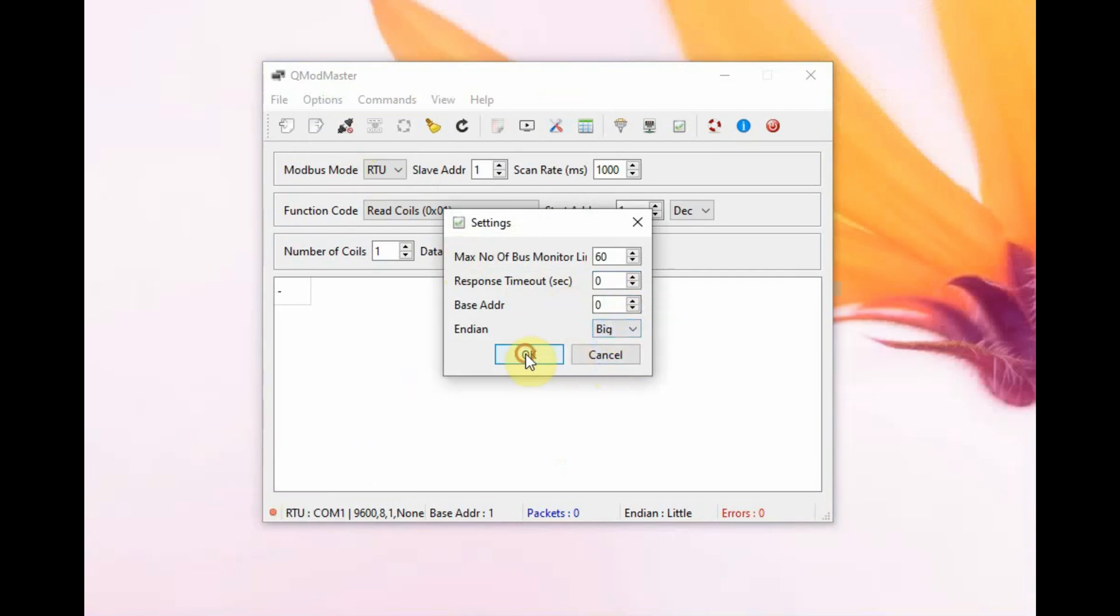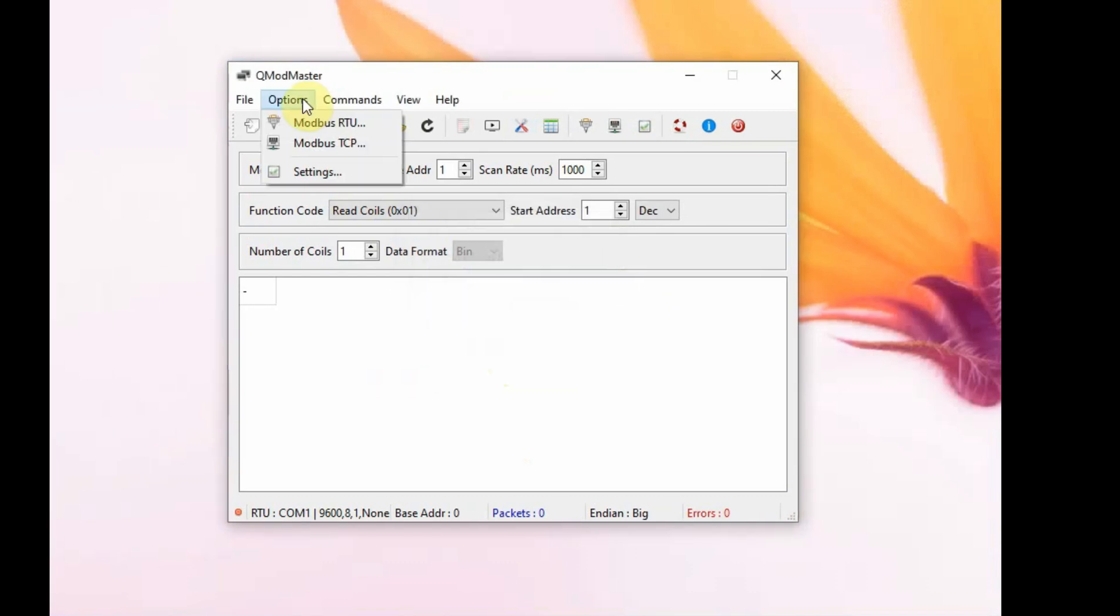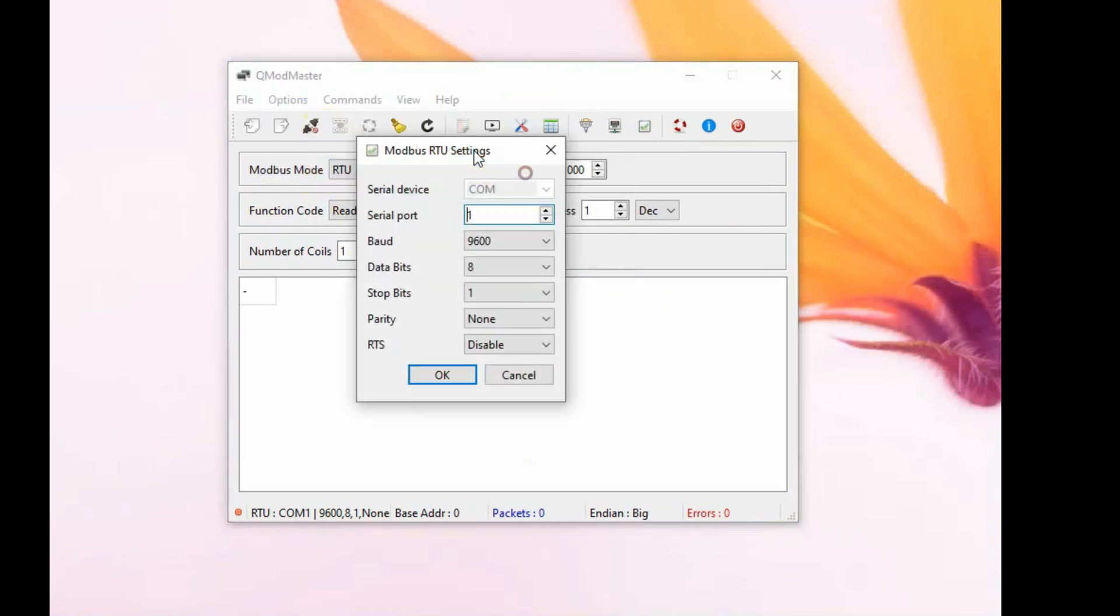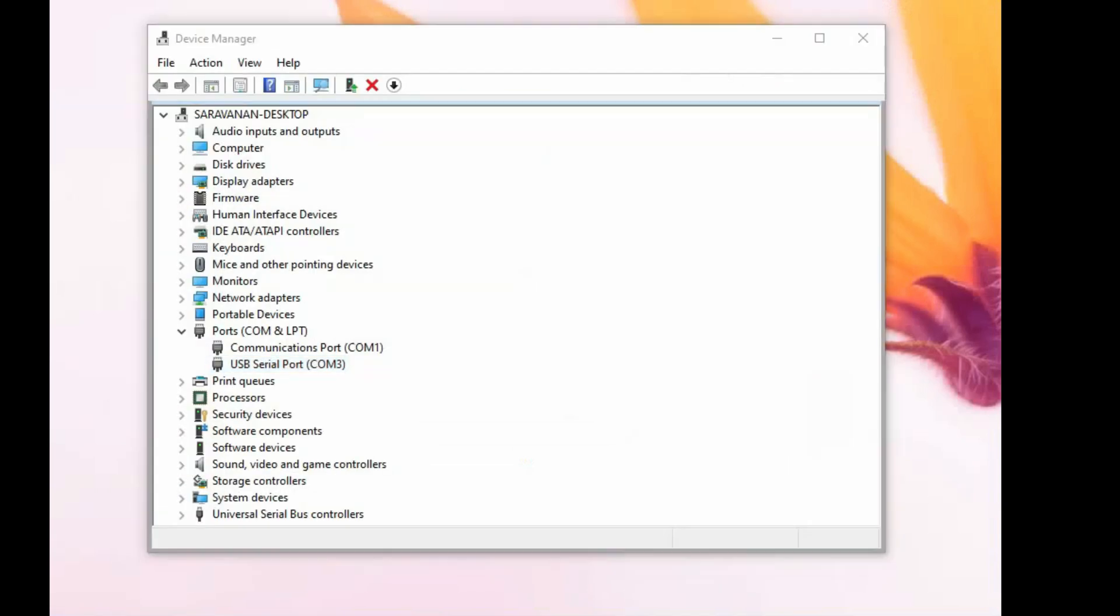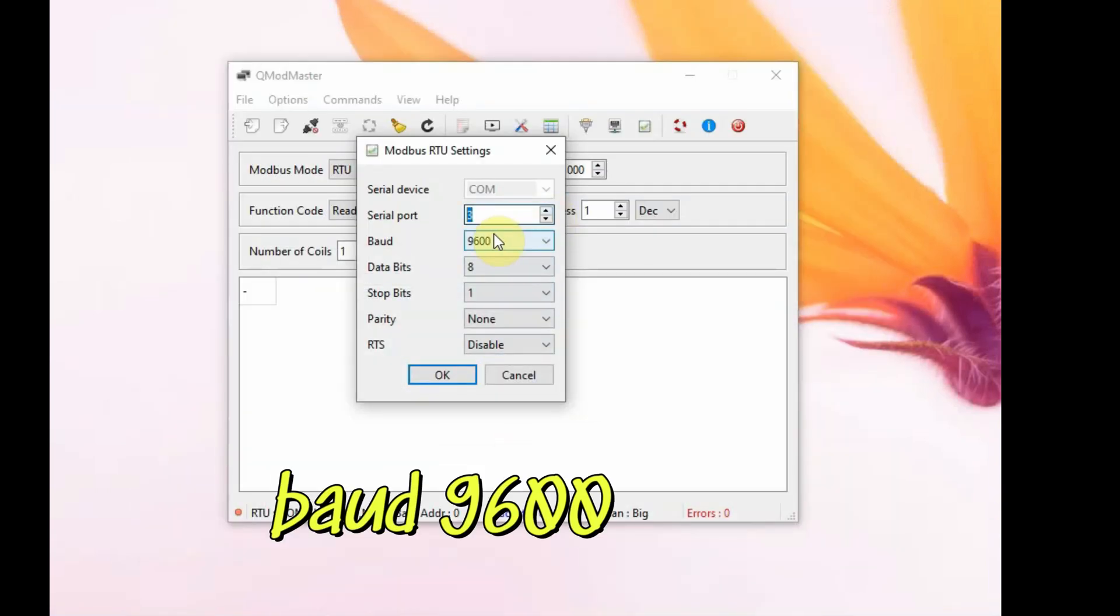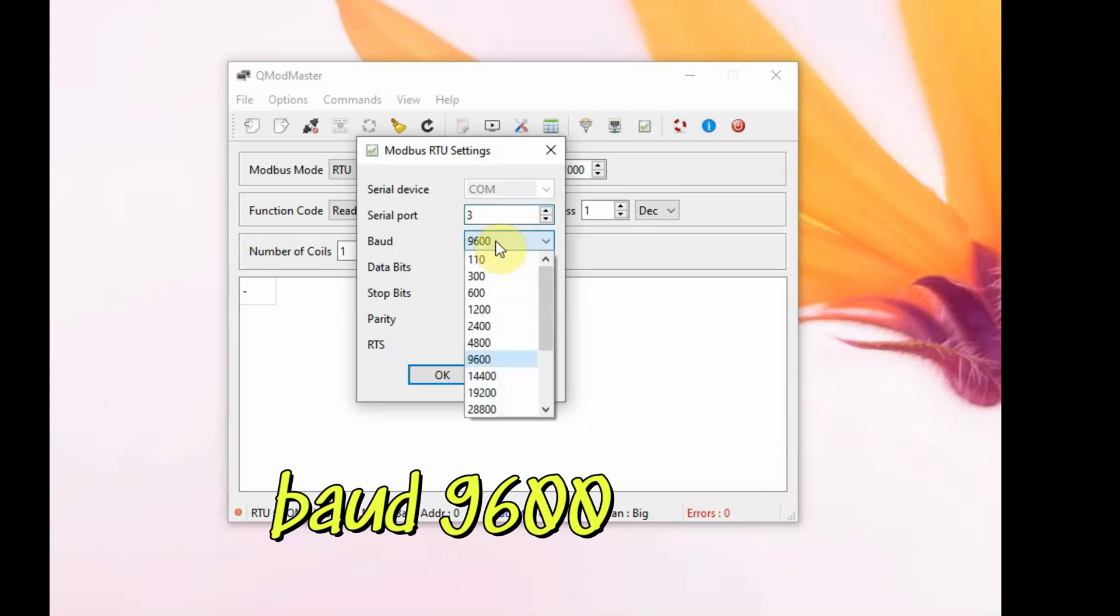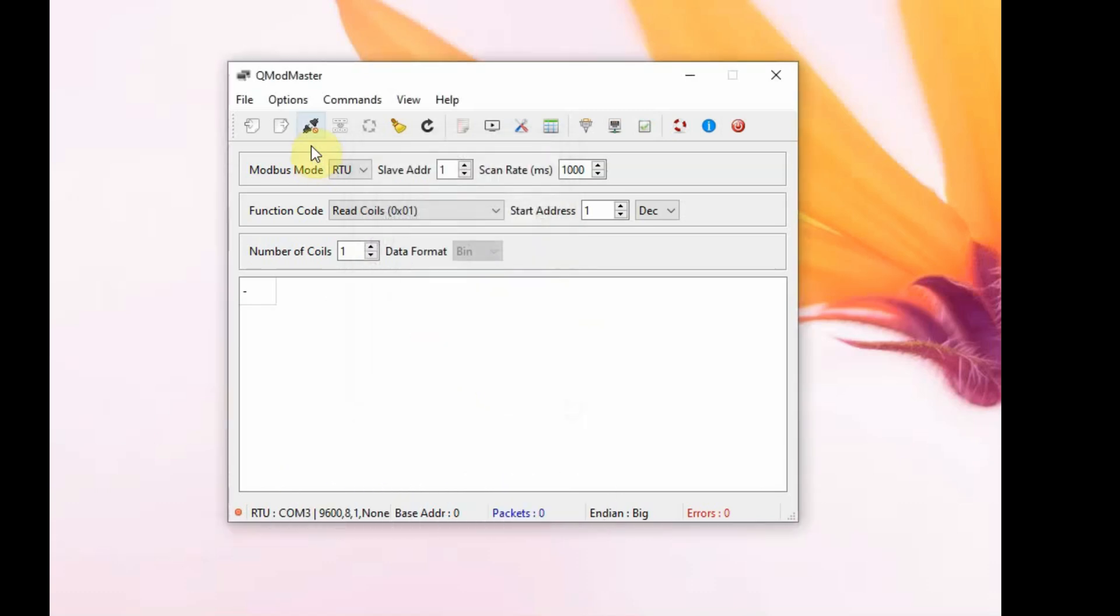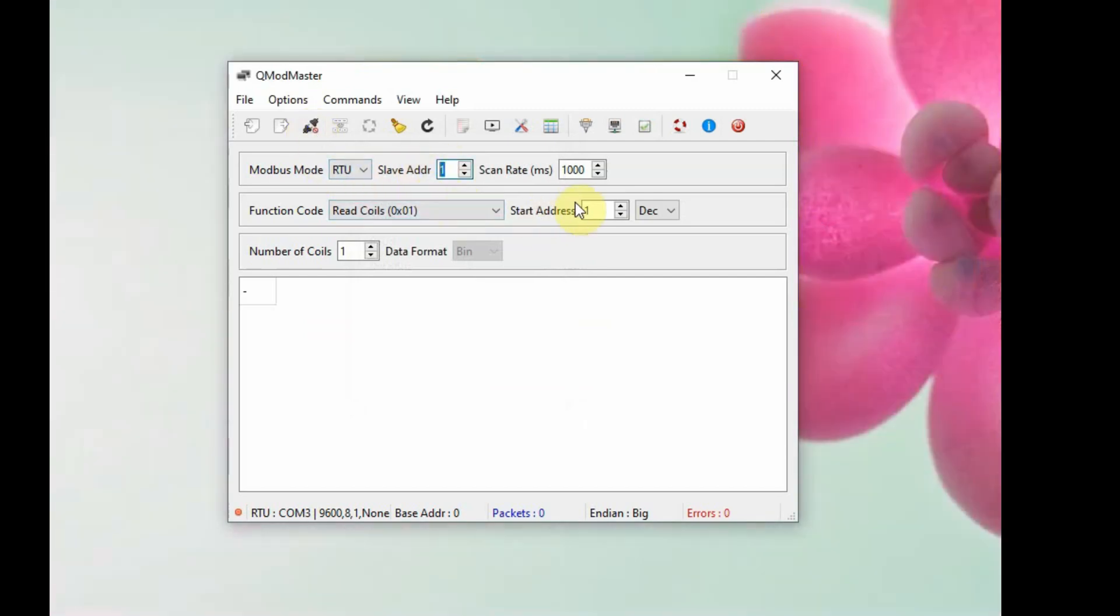The baud rate is 9600 8N1. 9600 is the default baud rate of the SHT20 XYMD02. The slave address is 1, which is the default address of the module.